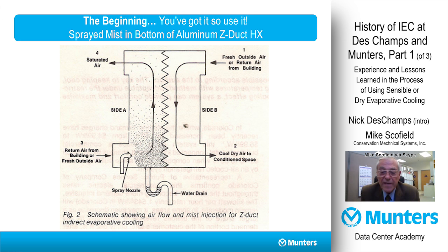At the time, we didn't realize some of the problems that come up when you atomize water and allow it to be sucked through a plate-type counterflow air-to-air heat exchanger. The dry-to-dry performance of this heat exchanger is roughly 60%, but by introducing this water, we felt at least that we could increase the performance on the makeup air side by the difference of the wet bulb condition on the wet side to the ambient summer dry bulb, which in Denver is around 93 degrees.